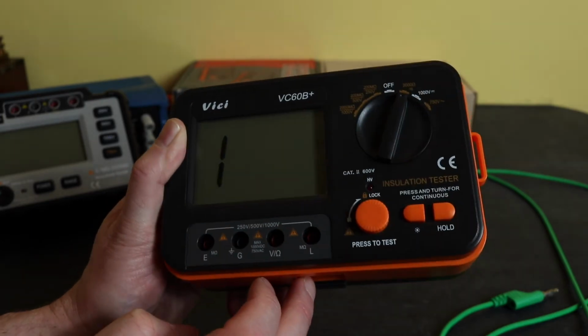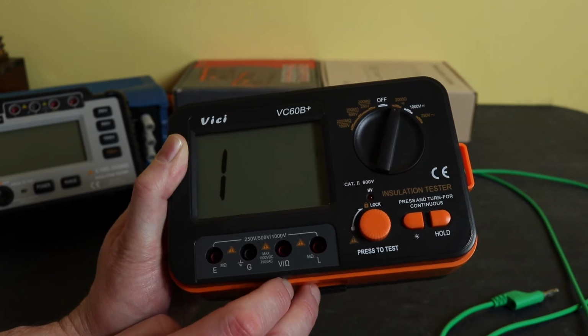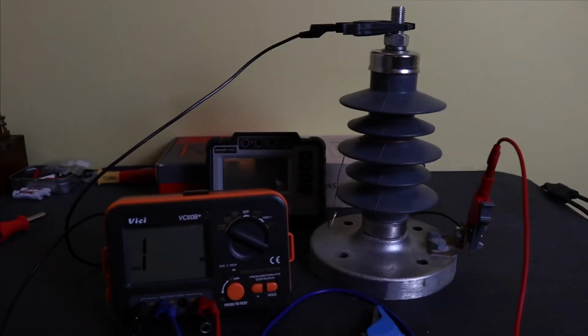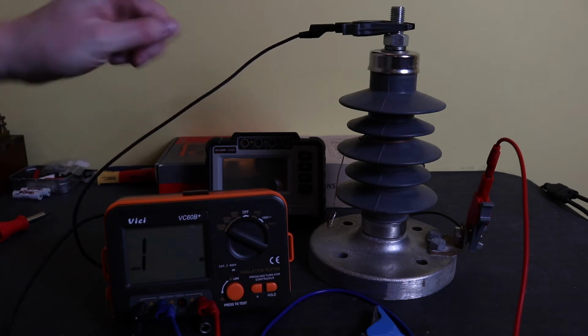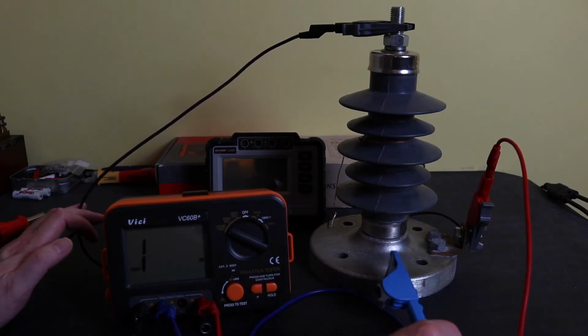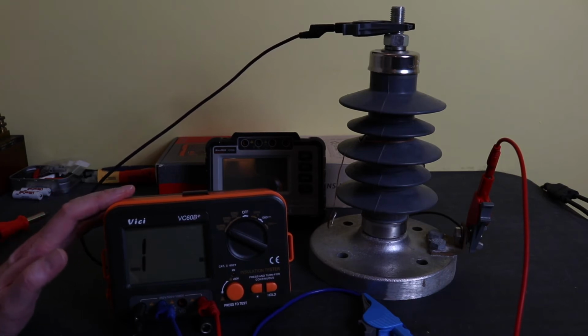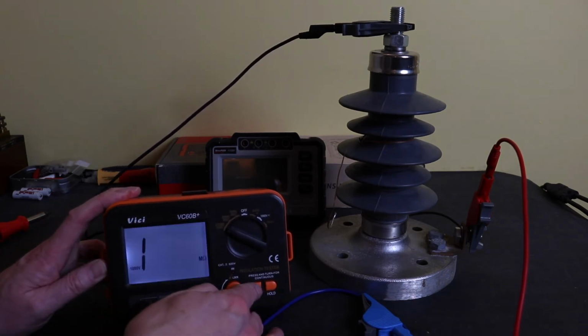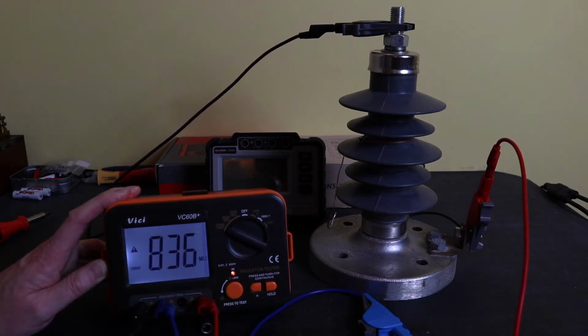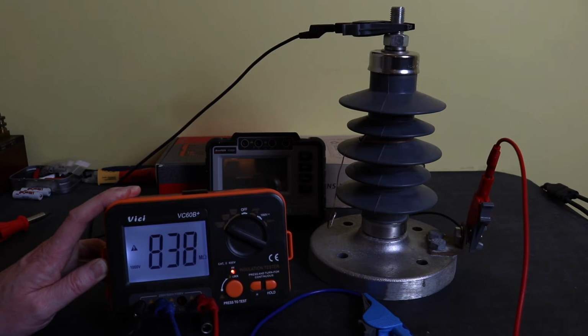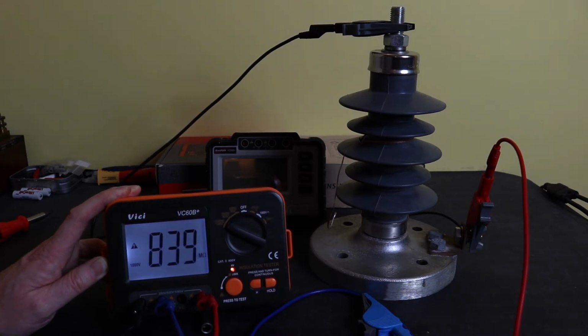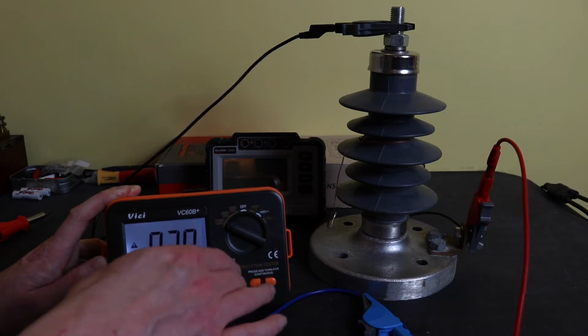Okay, so that's that done. We'll set up and we'll do a test with the guard terminal and see how we get on with that. Okay, so we'll give the guard terminal a test. This has to be done each unit individually, and it'll be done at 1000 volts. You can see I've got one lead connected to the top of the bushing, the lead connected to the earth plate, and then the guard terminal is currently floating and not touching anything. So we should be looking at around about 830 mega ohms when we test this, and we've got 838, 839. So that seems good.